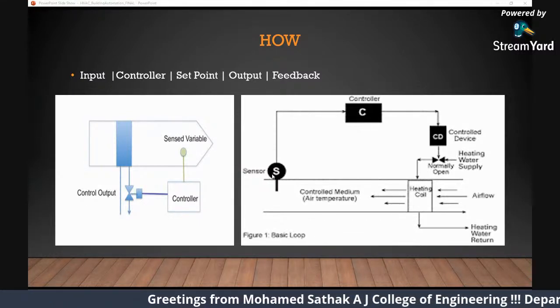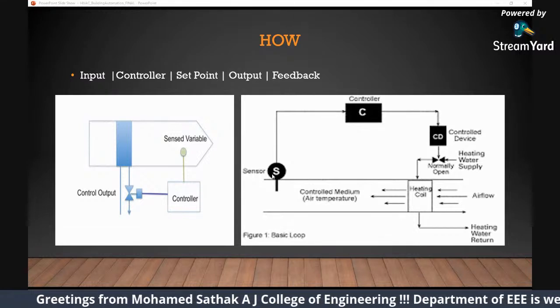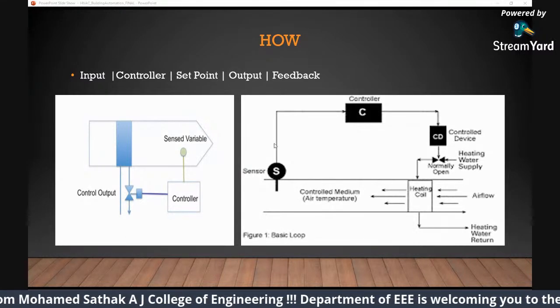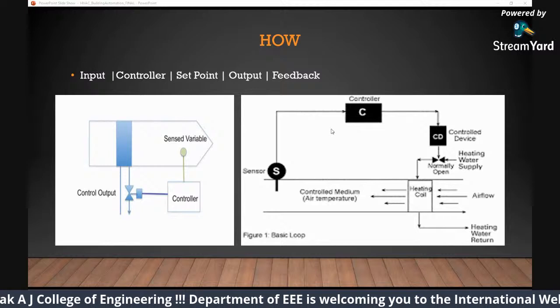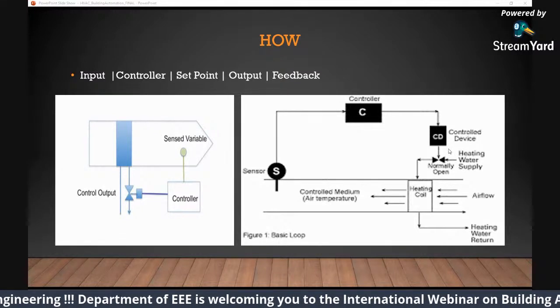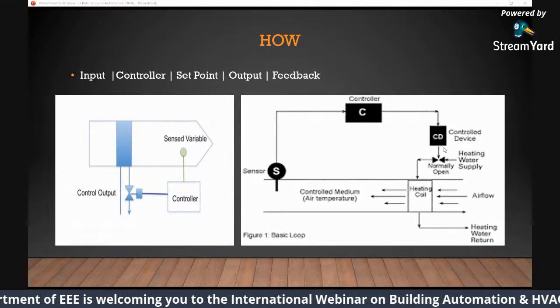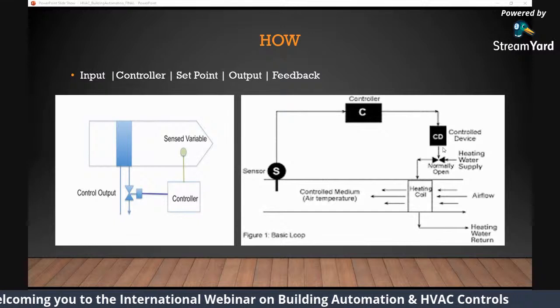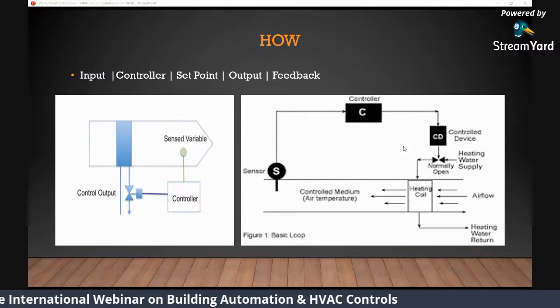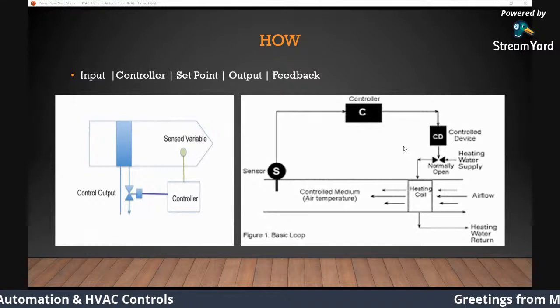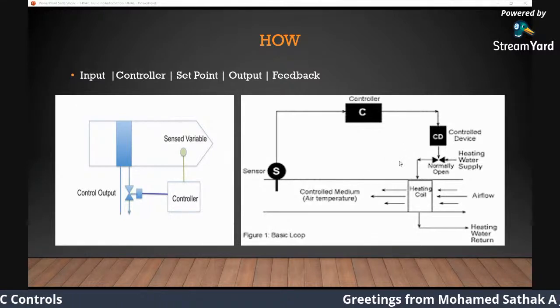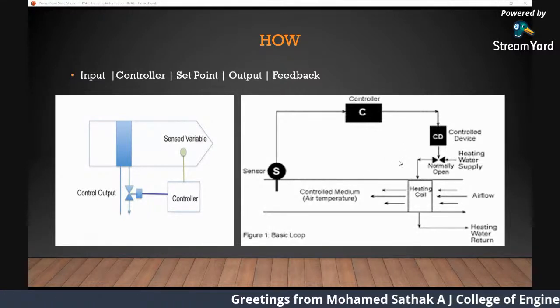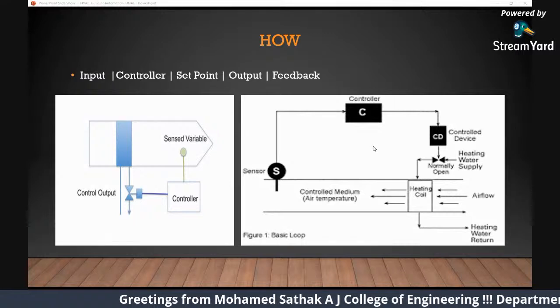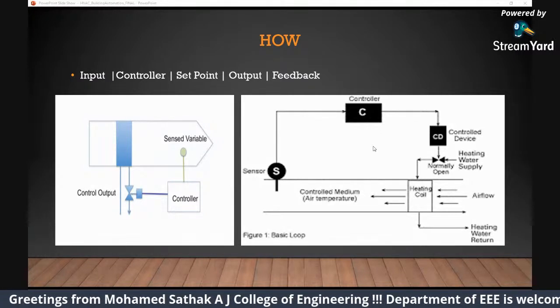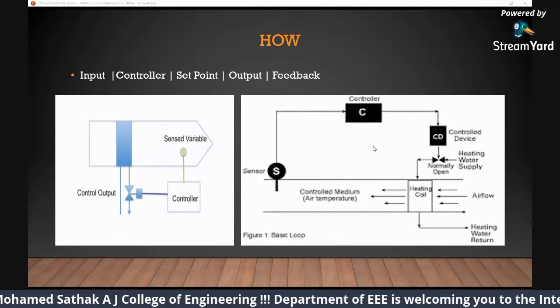So the sensor keeps measuring. If the temperature is too low, it gives feedback to your controller, and the controller gives output to your valve actuator. So the heating valve opens to the 100 percent position, and there is a lot of hot air from the heating coil. Now, when the sensor measures that it has reached the set point of 30 degrees Celsius, it gives feedback, and now it tries to close the valve. So that's the concept behind control feedback. Any doubt so far?